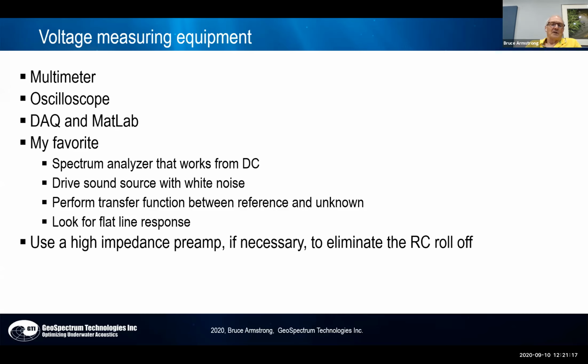Because if you recall the calibration curve that you saw for a hydrophone, it should be flat at low frequencies. So if I'm measuring a hydrophone at 1 hertz or 5 hertz or 10 hertz, it should be the same number. The one little caution is that piezoelectric hydrophones will roll off if they're driving a low impedance, and most of these things are 1 megohm impedance. So if you have a normal hydrophone, you're going to have to put a high impedance preamp in there to stop it from rolling off. Either that, or you collect the data and analytically correct for the roll-off that's occurred.